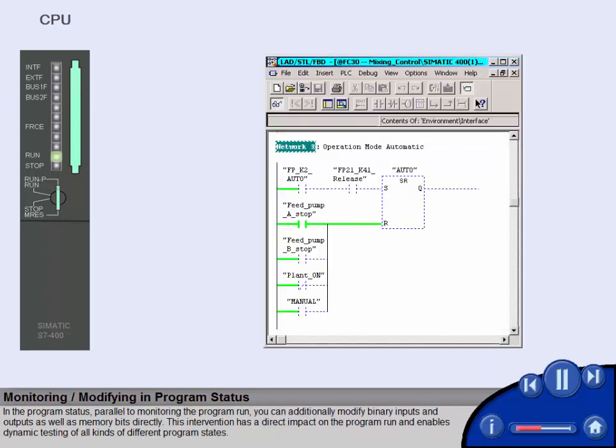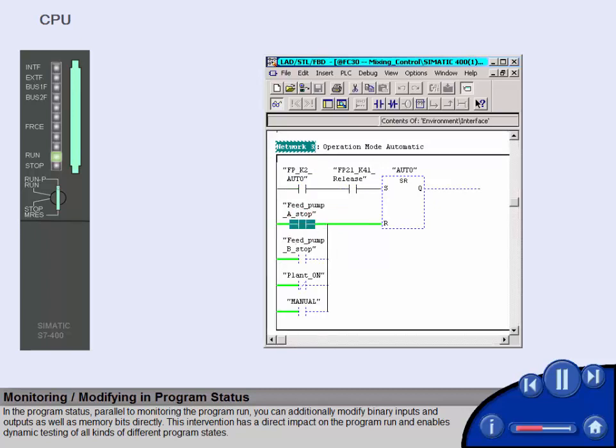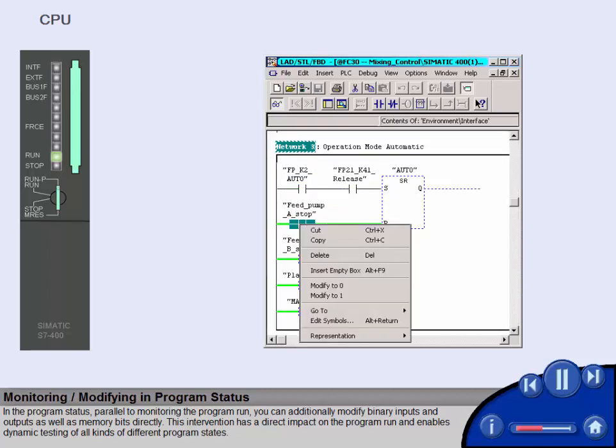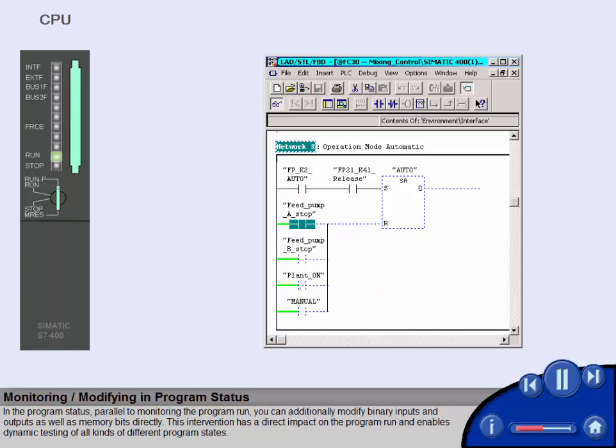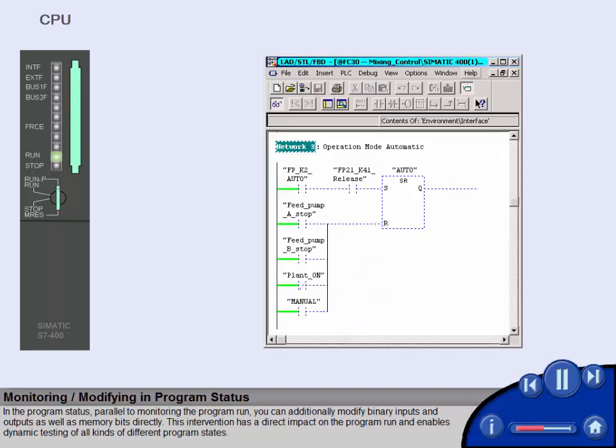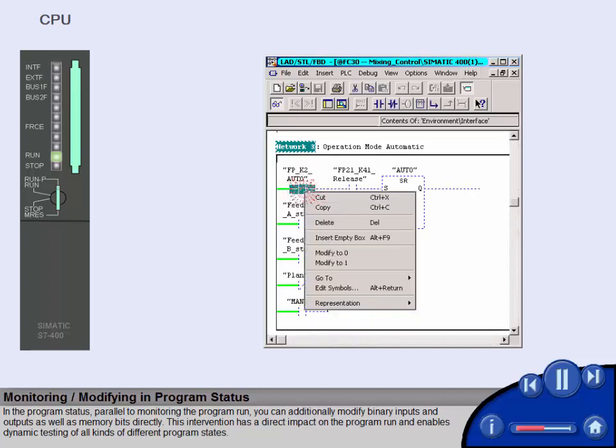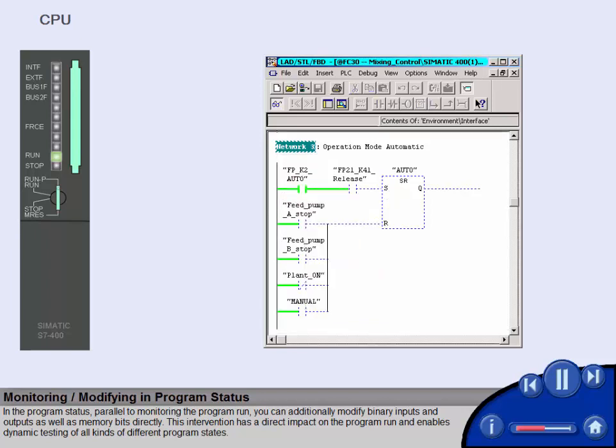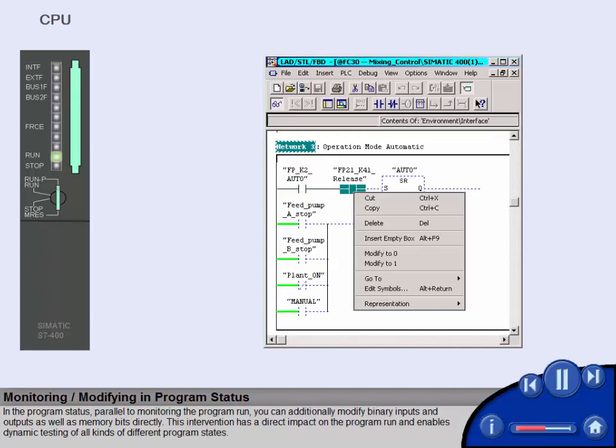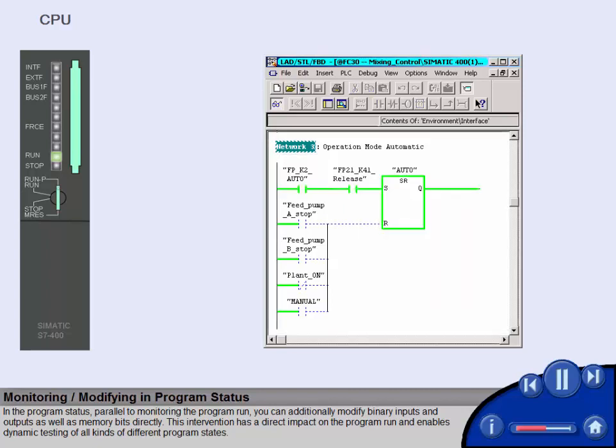In the program status, parallel to monitoring the program run, you can additionally modify binary inputs and outputs as well as memory bits directly. This intervention has a direct impact on the program run and enables dynamic testing of all kinds of different program states.